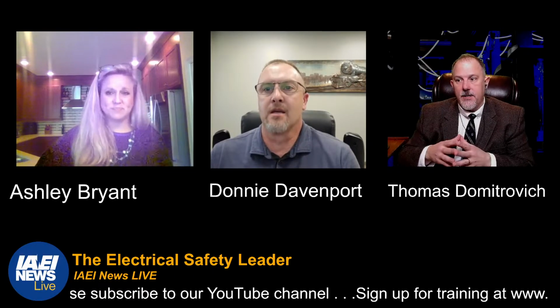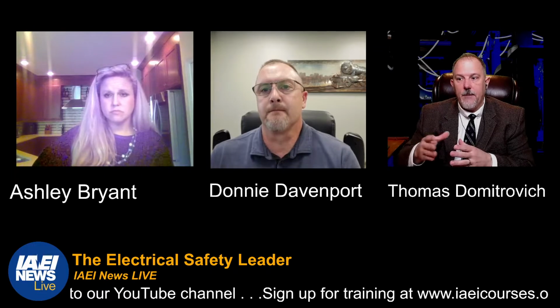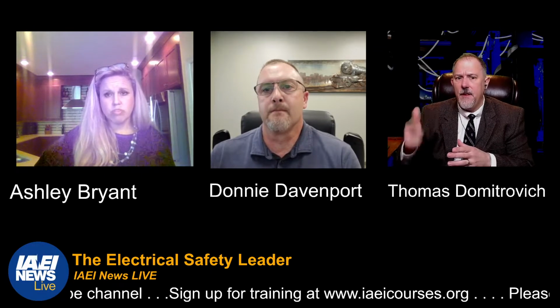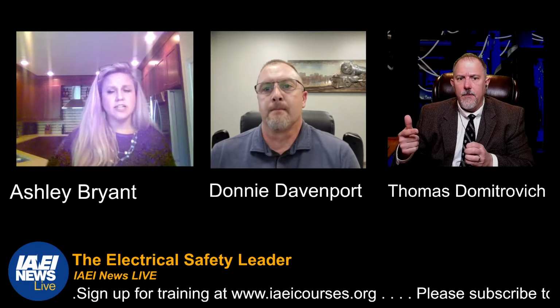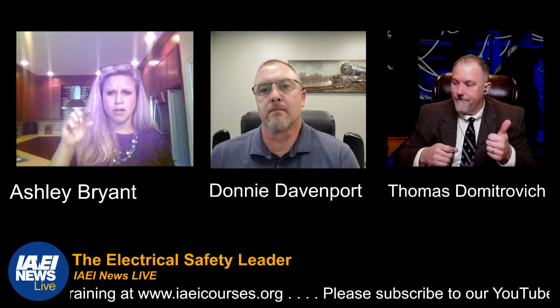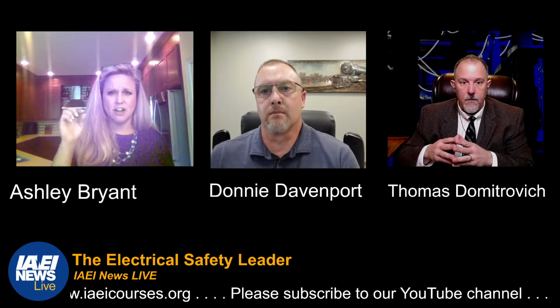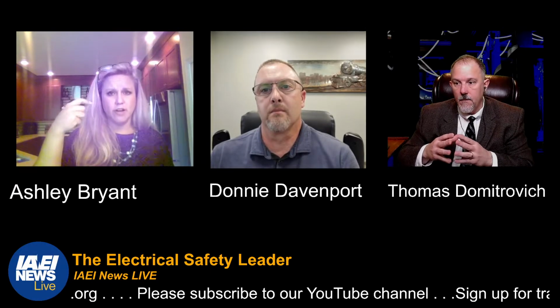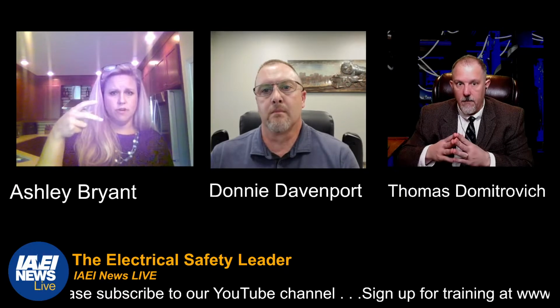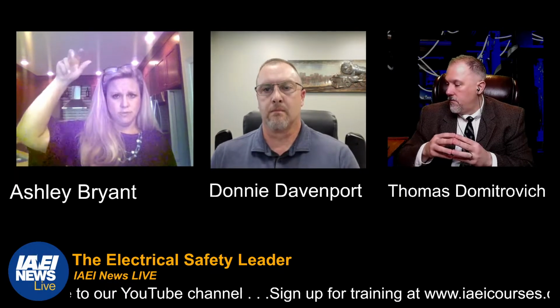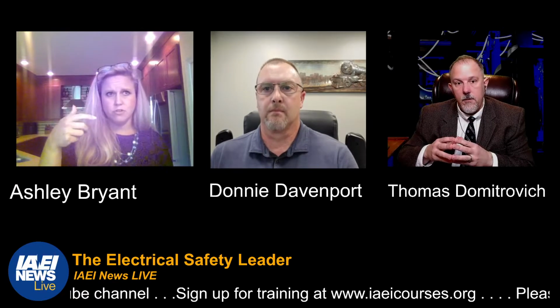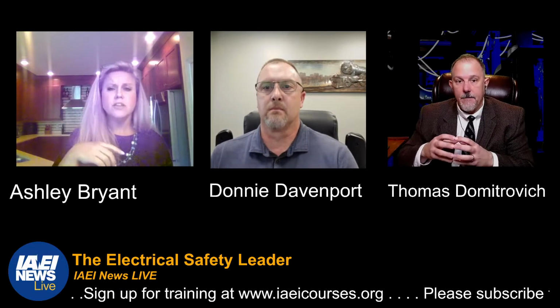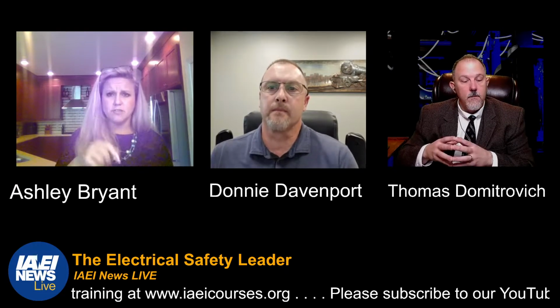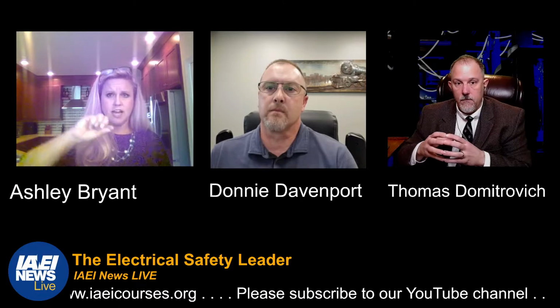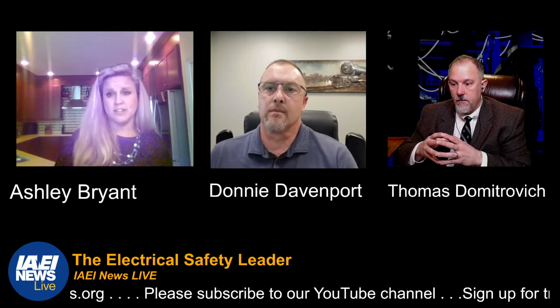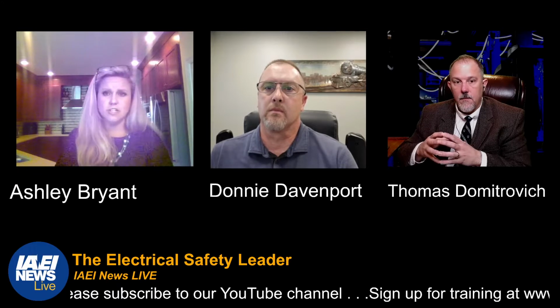Now Vincent Coley asks, do the combination AFCI, GFCI breakers get wired the same way? And Ashley, I think you touched on that. I did—the dual function or dual purpose circuit breakers that have the AFCI and GFCI technology in them have a hot lug and a neutral load lug, so your hot wire and your load neutral have to come to the breaker. That's because there's GFCI technology in the breaker, and the GFCI is measuring what goes out must come back in—you've got to complete that circuit for that technology to work.